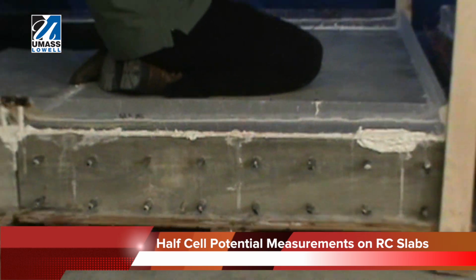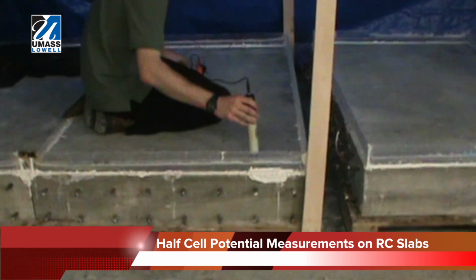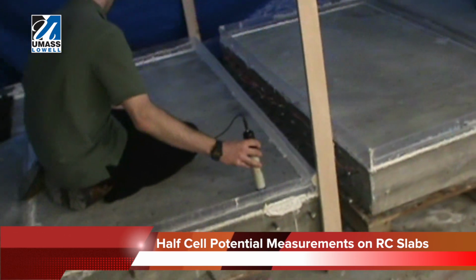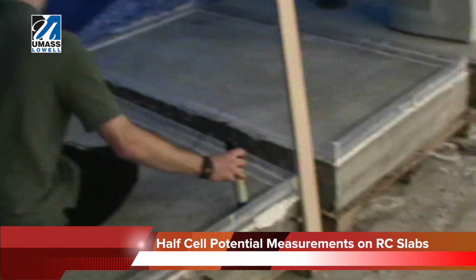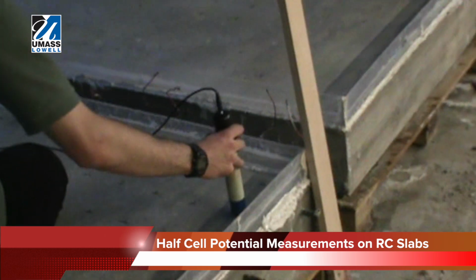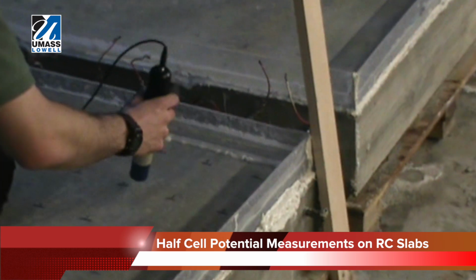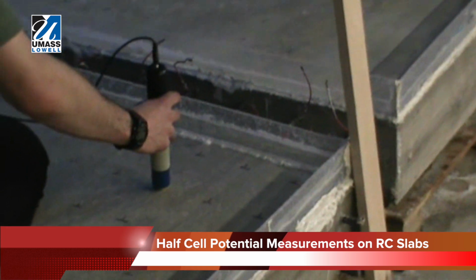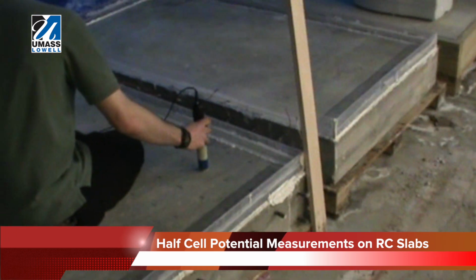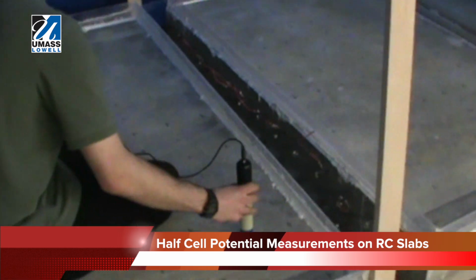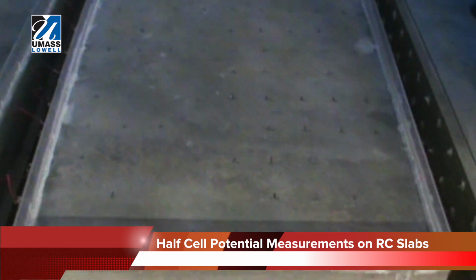We would connect a red wire coming out of the reference electrode to the rebar that you see here in the picture in the top node, and the black line with the reference electrode that you see in Alice's right hand. If we have a fluctuation of plus or minus 20 millivolts in the half-cell potential measurements, we should not use the data. Conversely, if our data fluctuates less than 20 millivolts, the data is good to use.